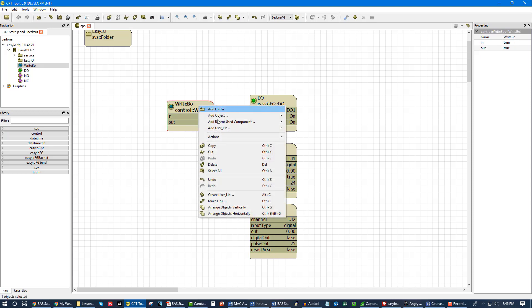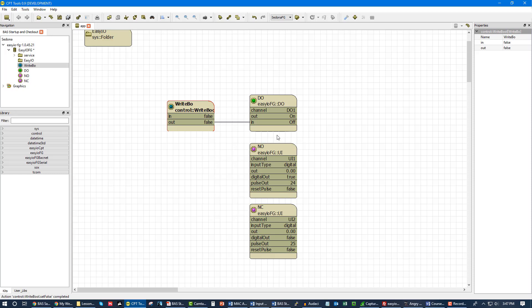Now I can go right here once again, set this to false, relay turns off and now we see our normally open is false and our normally closed is true. That is how dry contacts work, that is how you wire them up and this is what they look like inside of the controller software.